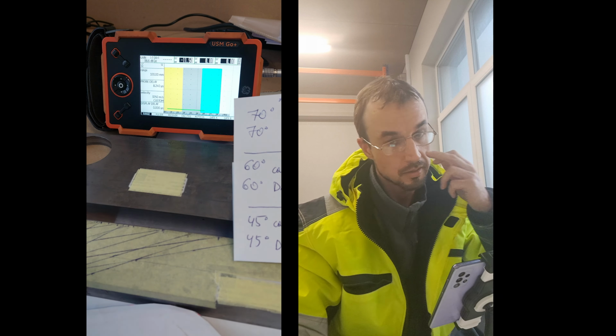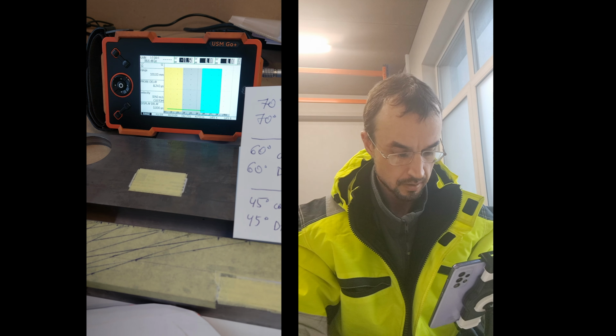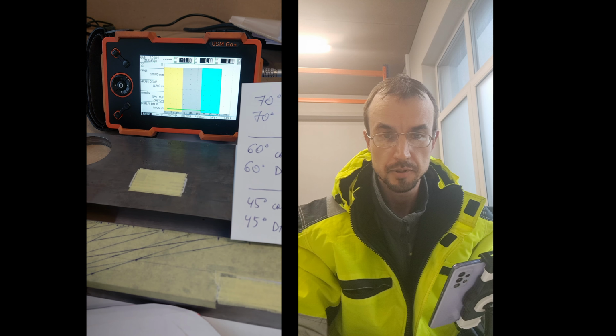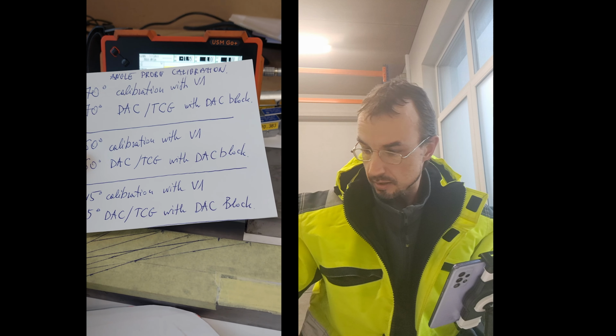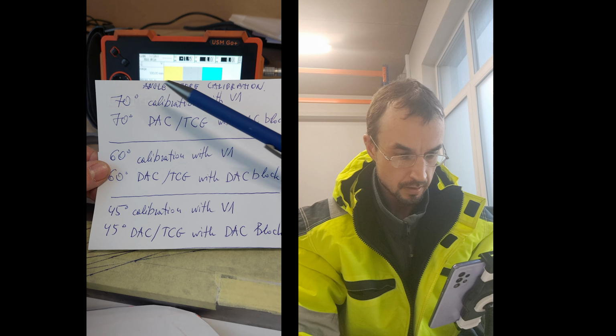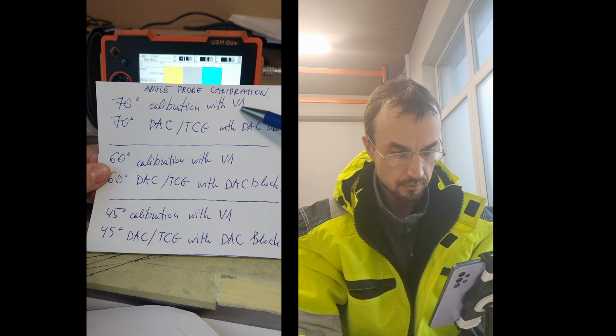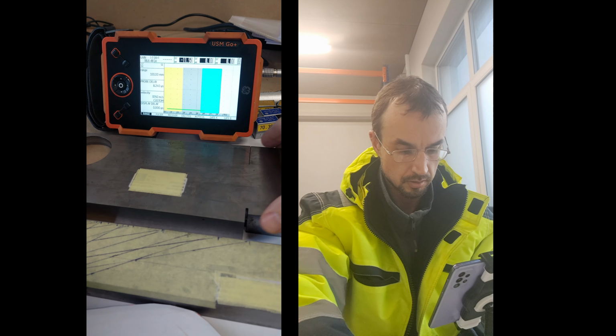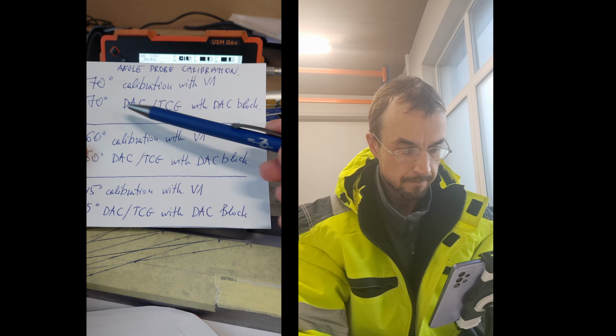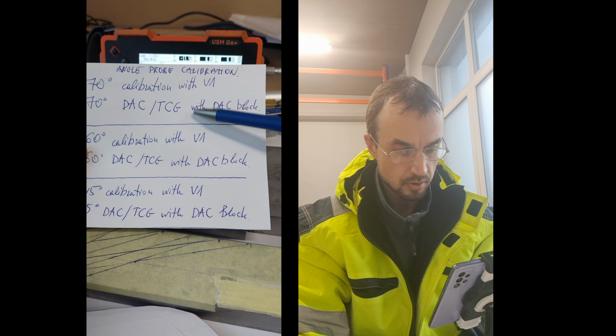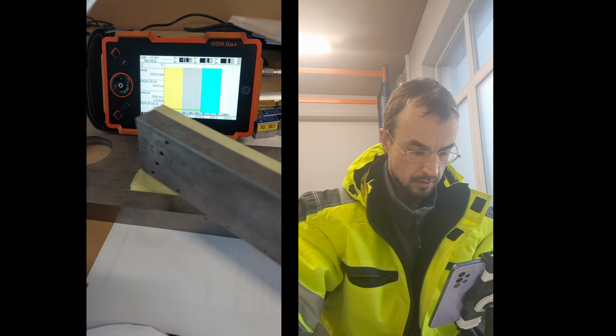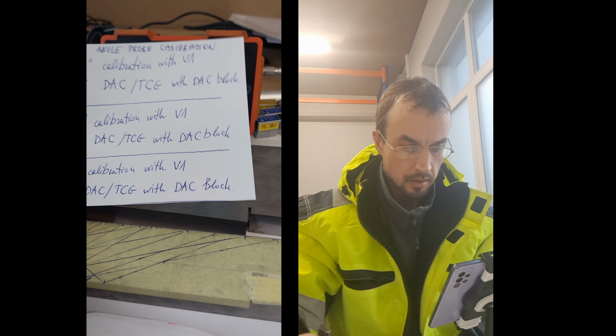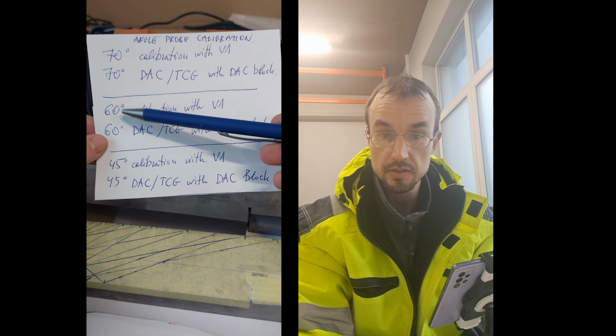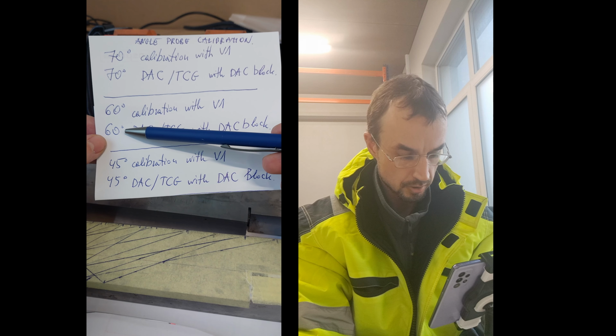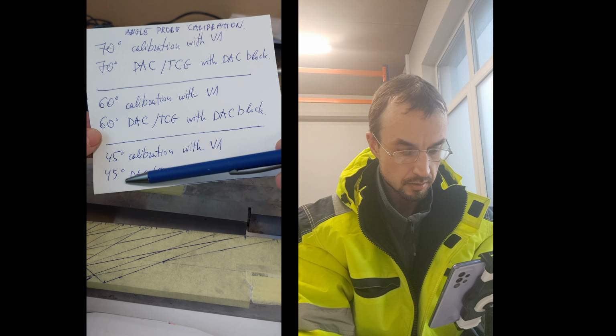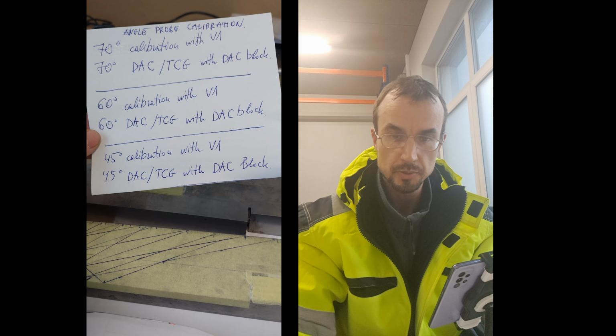I'm starting the new part, and that is angle probe calibration. The plan is like this. I'll be doing 70-degree probe calibration with calibration block number 1. Then I'll do the DAC/TCG with the DAC block, this thing. Then the next one is repeating the same thing with the 60-degree probe. Then after that, repeating the same thing with the 45-degree probe.